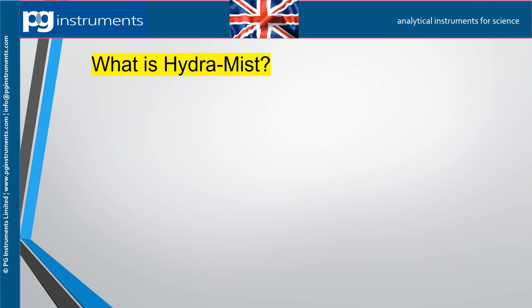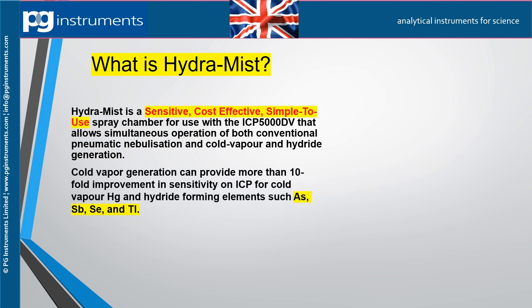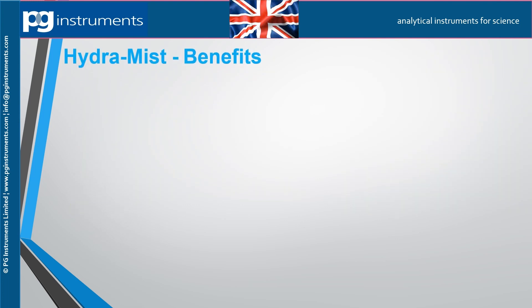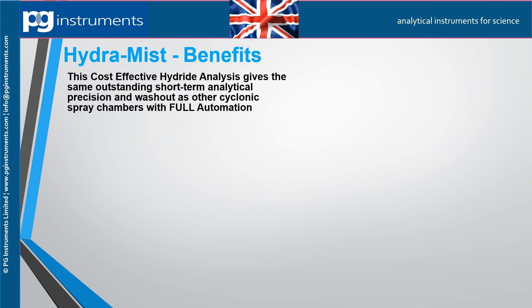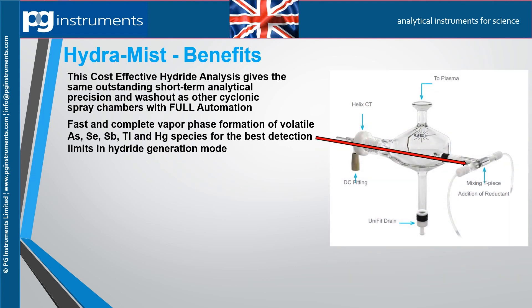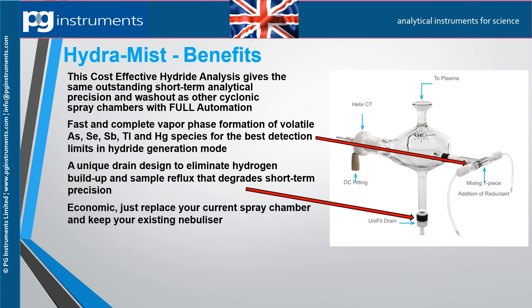Hydra-Mist is a sensitive, cost-effective, simple-to-use spray chamber for use with the ICP-5000DV. It allows simultaneous operation of both conventional pneumatic nebulization and cold vapor and hydride generation. Cold vapor generation can provide more than a tenfold improvement in sensitivity for mercury and hydride forming elements such as arsenic, selenium, and antimony. It delivers outstanding short-term analytical precision and washout, with fast and complete vapor phase formation of volatile arsenic, selenium, antimony, thallium, and mercury species.